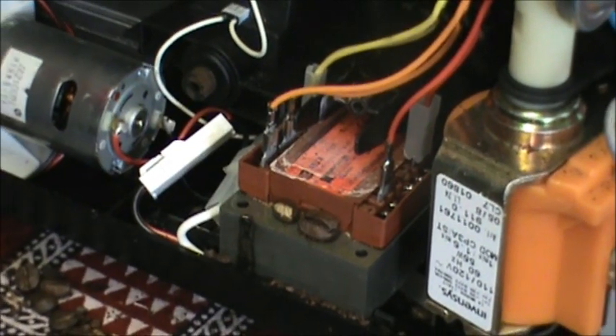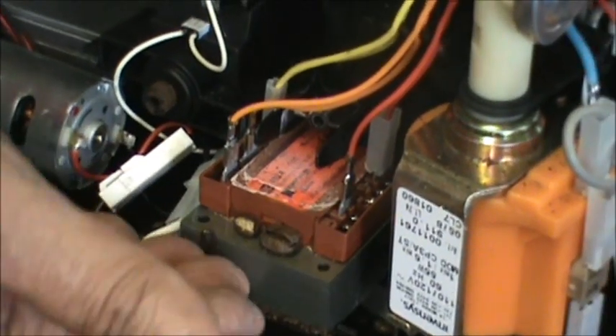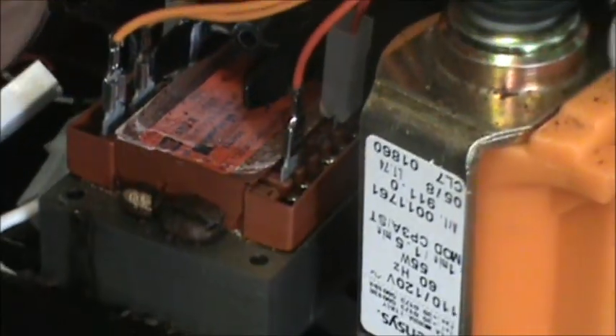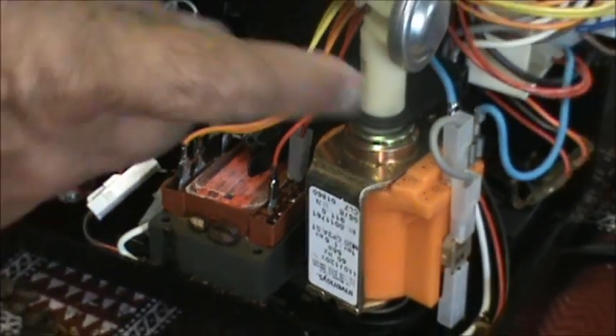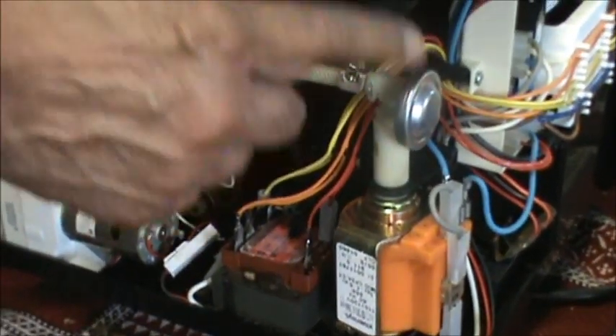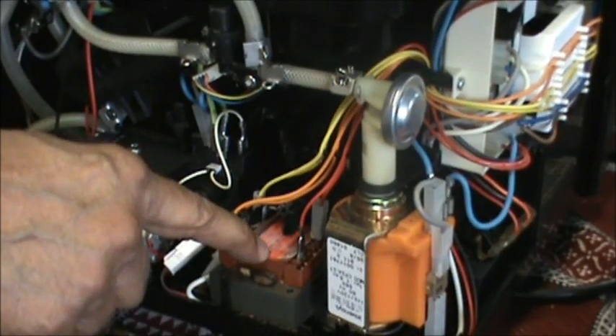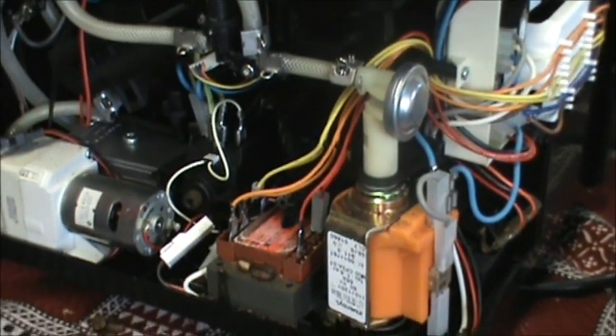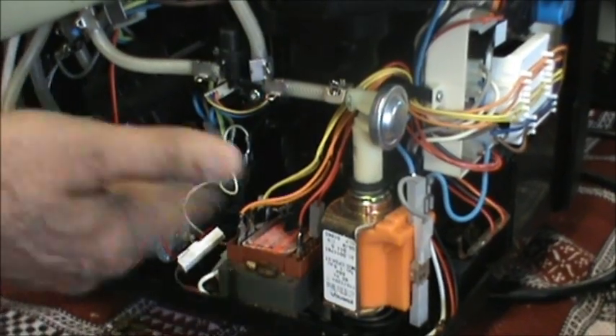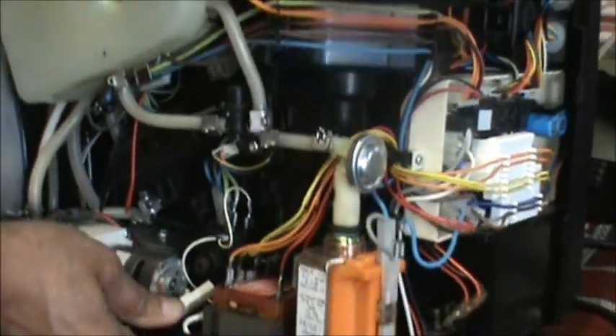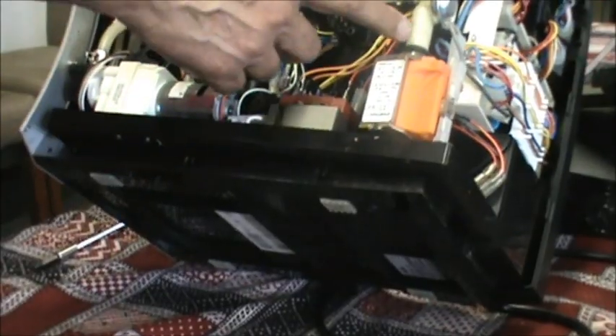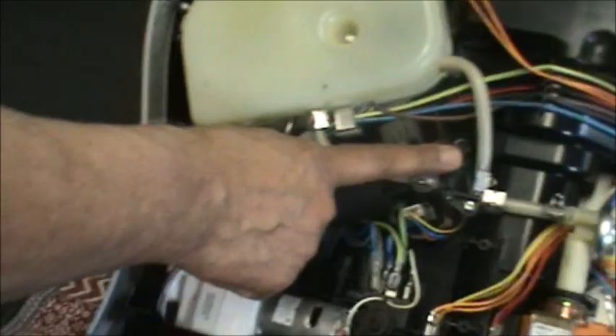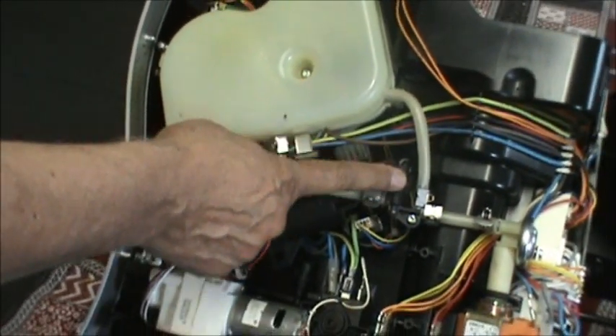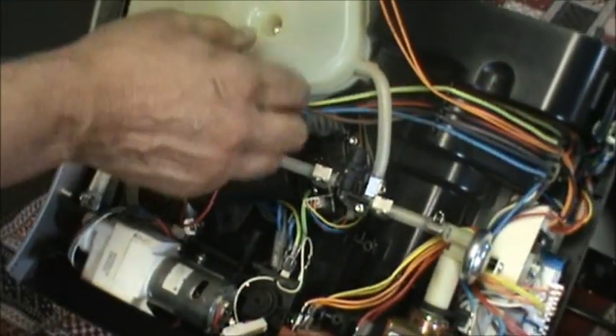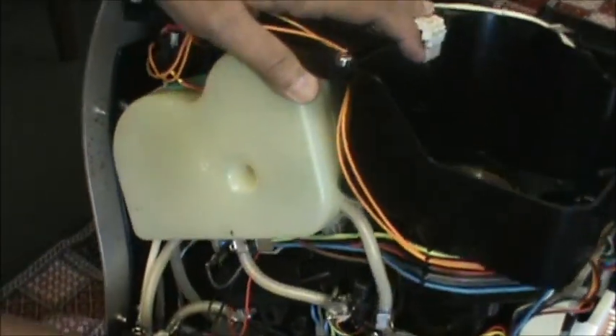What we feel is an odd location is for the transformer to be next to the pump and this membrane regulator, because this is a frequent cause of leakage. Water will drip on the transformer, and we have had several cases of transformers shorting, and we had to replace those. So the connections then here, they go from the membrane regulator to the high pressure check valve, and from there, let me remove this boiler.